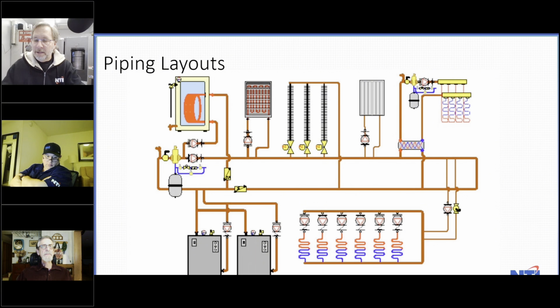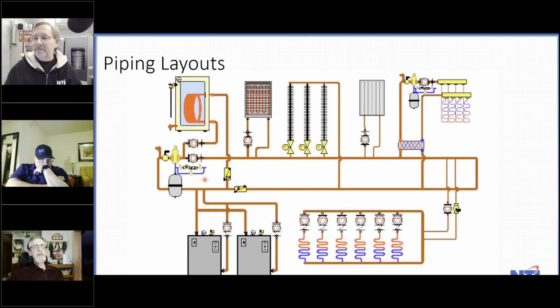And now I'm going to give this one to Ted, because this is Ted's drawing, and Ted can tell us what's going on here. Well, this is an old drawing, but we've got 2 boilers with multiple loads. So 2 boilers are piped in parallel, so one doesn't compete with the other. They're injecting into a primary loop with closely spaced T's.